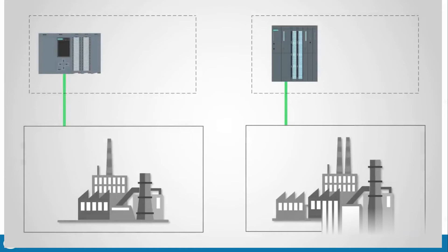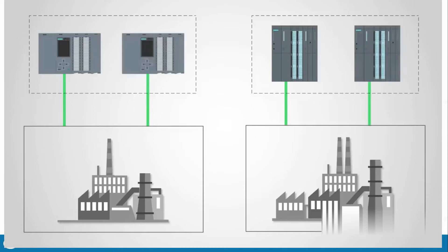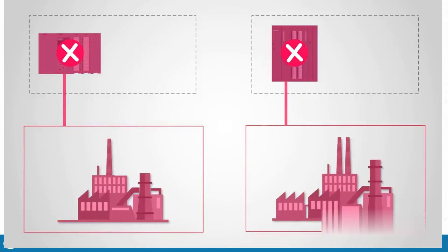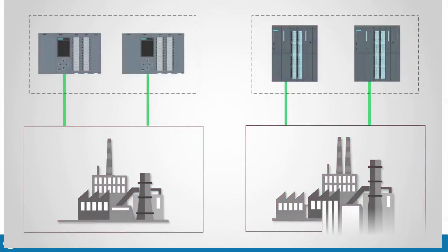There are indeed scenarios in which a PLC system would be the best option, such as smaller sized processes where you could employ redundant components to negate the possibility of process shutdowns. Without redundancy, you risk production halts due to the nature of a single processor controlling an entire plant. Redundancy may be deployed in either the PLC or DCS applications.